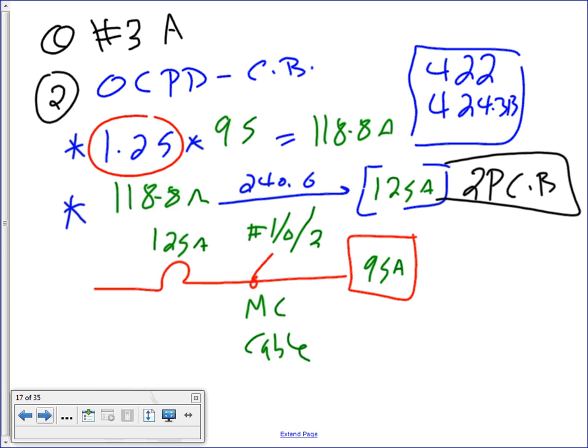Okay, so we size, any questions, guys? We size the overcurrent protection device. We size the conductor. Why did I multiply by 1.25? If you go to 424.3(B), it will tell you it's a continuous load, heating element, multiplied by 1.25. Unlike water heaters on appliances, where they allow you to go 1.5. Go figure.